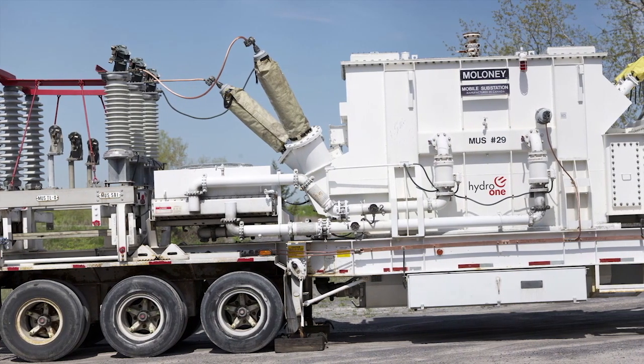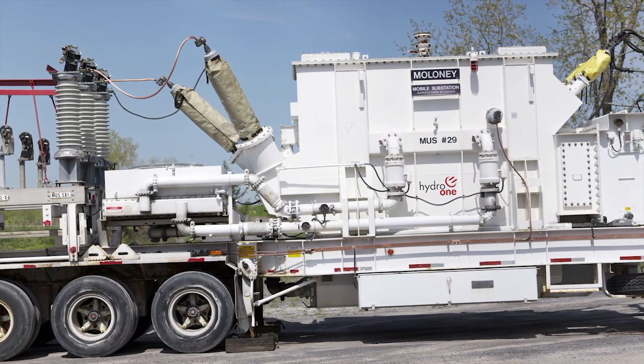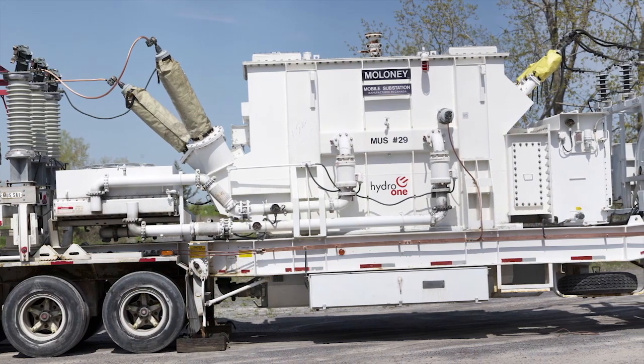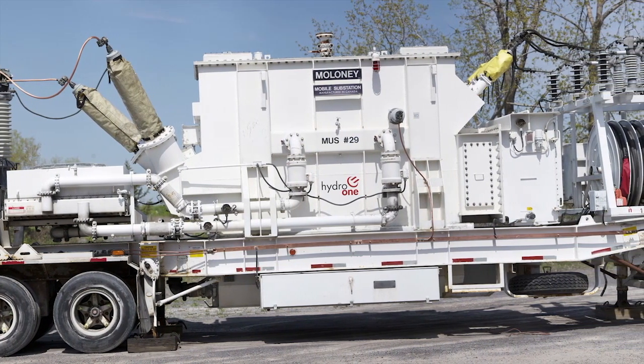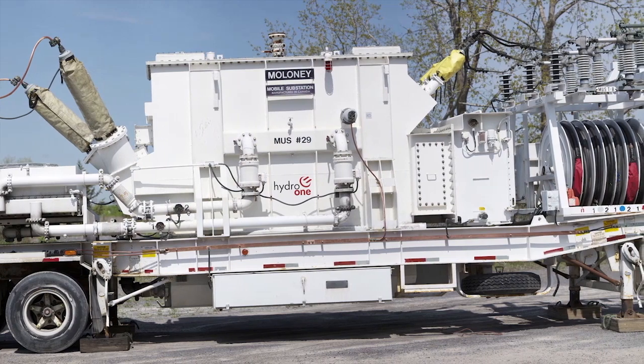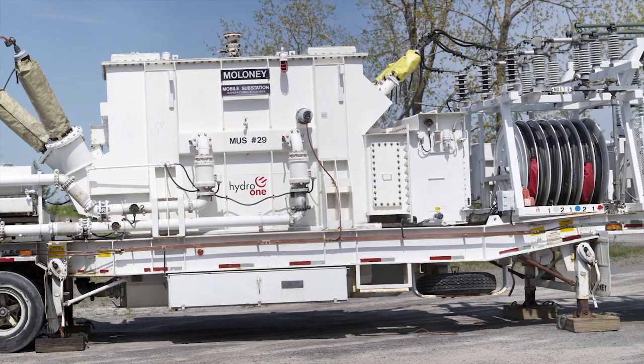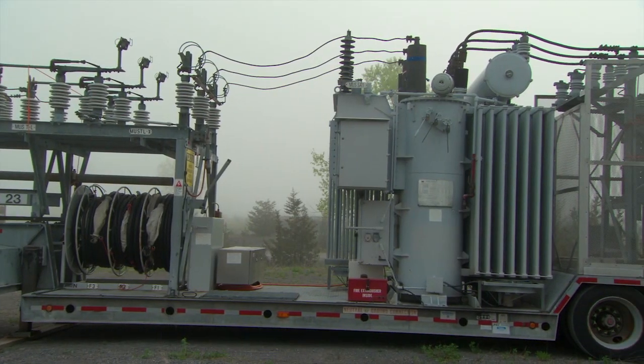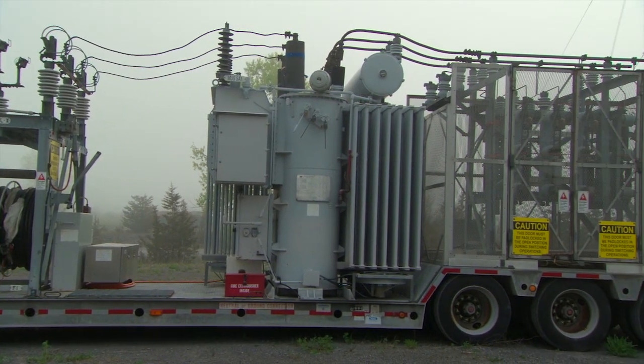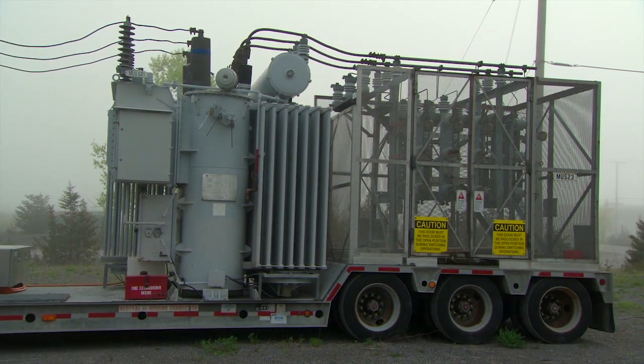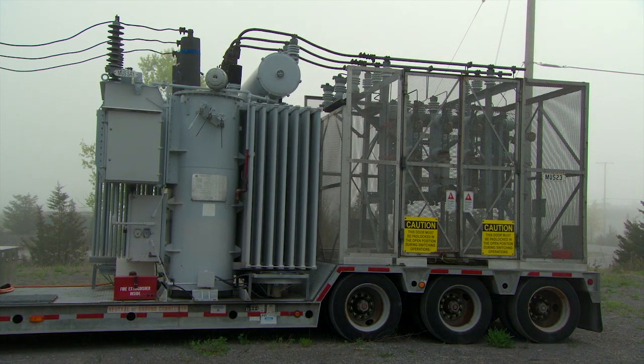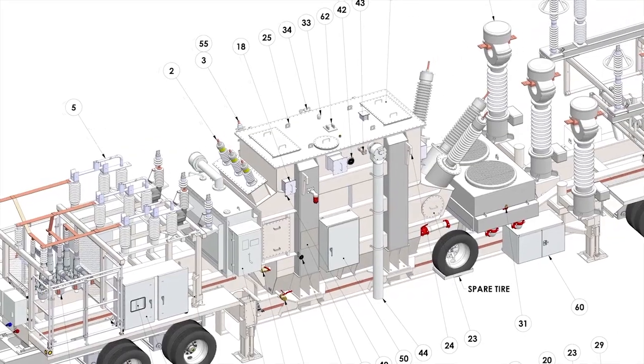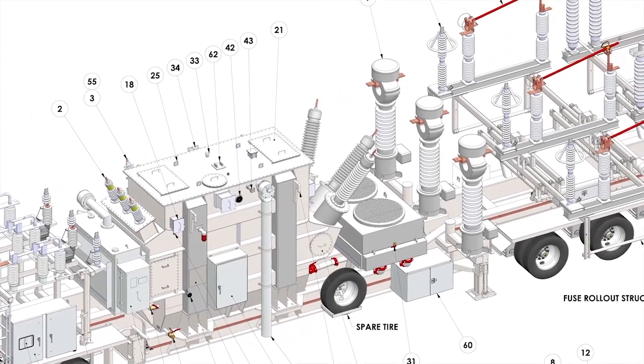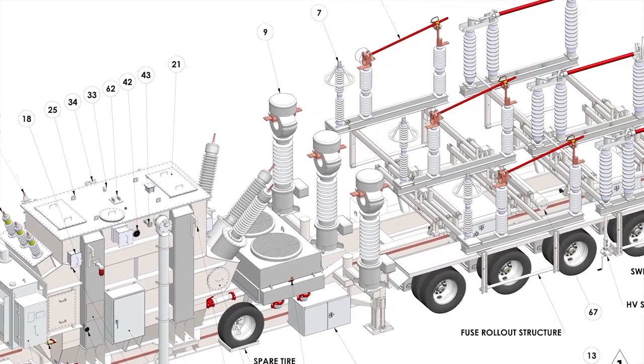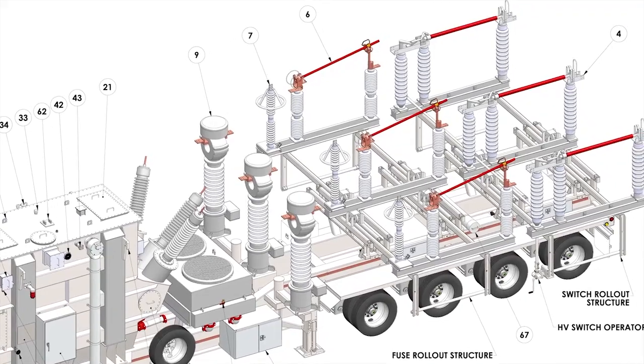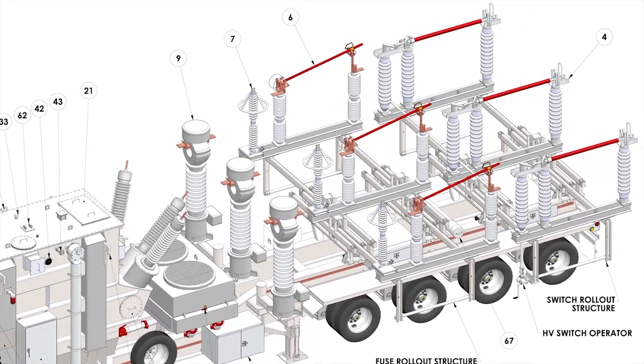Hydro One currently has a fleet of 28 mobiles. These units have available primary voltages of 115 kilovolts, 44 kilovolts, and 27.6 kilovolts. Many of the 44 kV and 27.6 kV class mobiles are also capable of dual primary connections, including 22 kV or 13.8 kV. Due to the increasing distribution program, we are procuring new mobile units and refurbishing existing ones. Let's start by reviewing some basic MUS components.